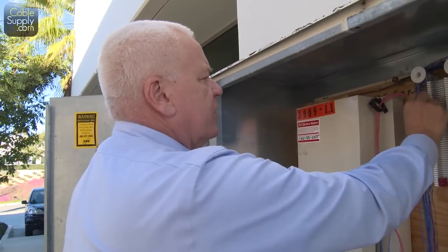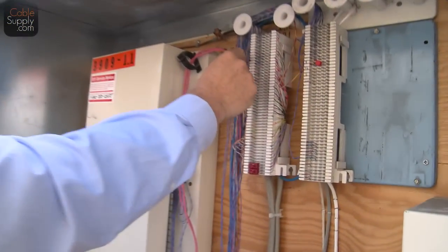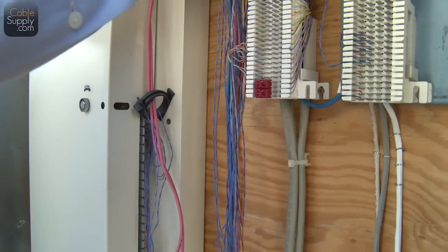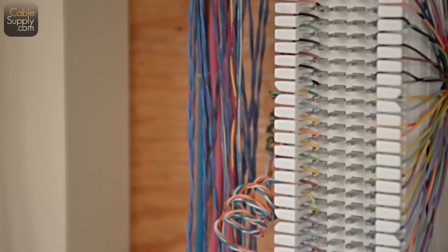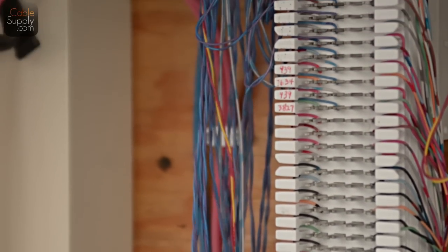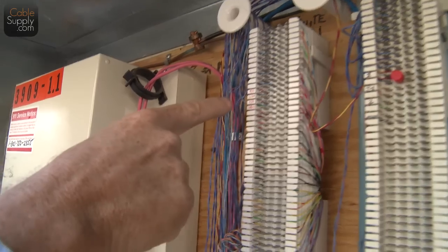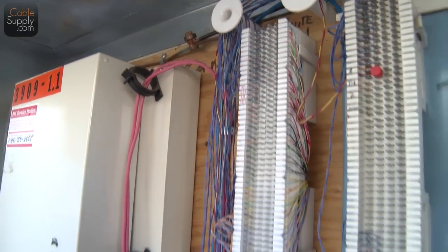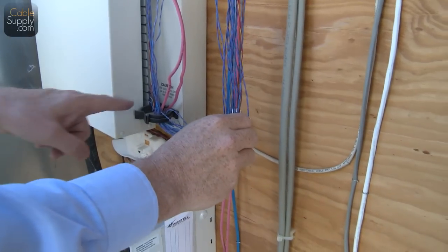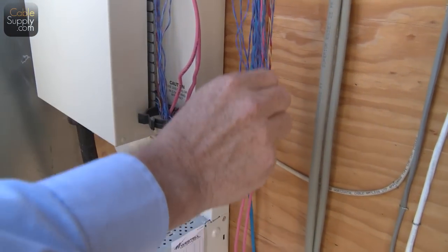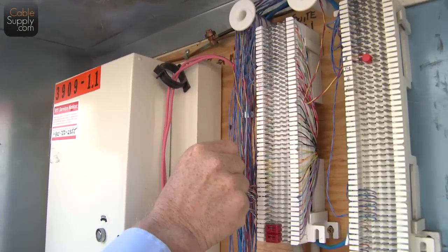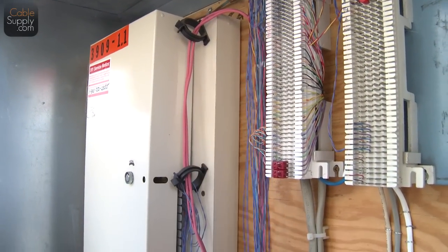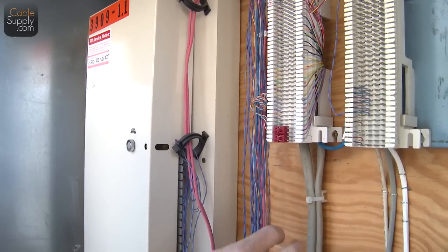One of the things you notice here is they put a little loop in here, and this is on purpose. If you take this and wiggle the cable up here, that means I can find the cable here, and watch this up here. You see? I can verify that that's the cable I'm pulling. I could read what it goes to, and then I can take it down here and pull, and I can see it goes right into here. So that's how you trace the cable when it's part of what's called a cross connect. This is a cross connect. All these cables here are part of a cross connect.